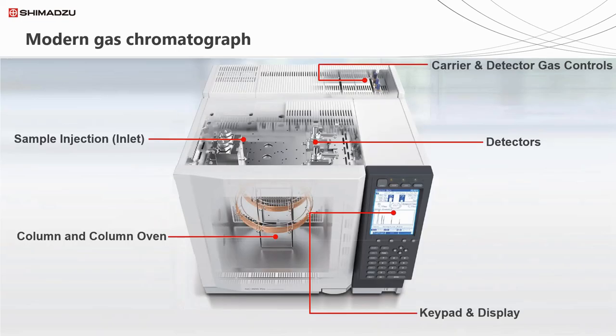Here's what a modern GC would actually look like. Inside the GC oven, we can see our column or columns. The GC is typically controlled by a keypad or display on the front, although many are now controlled by a PC remotely. The sample injection inlet and the GC detectors are usually in the roof of the GC. The carrier gas controller - the step-down flow controller - is typically located in the back of the GC.